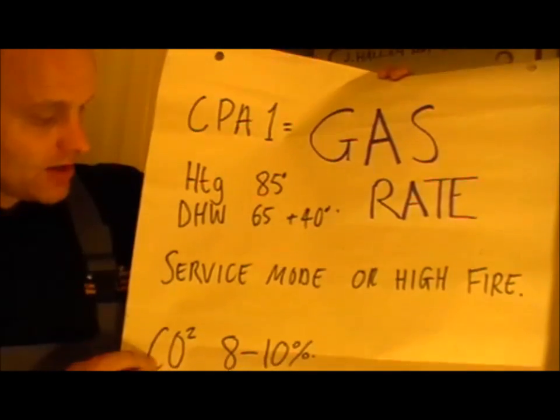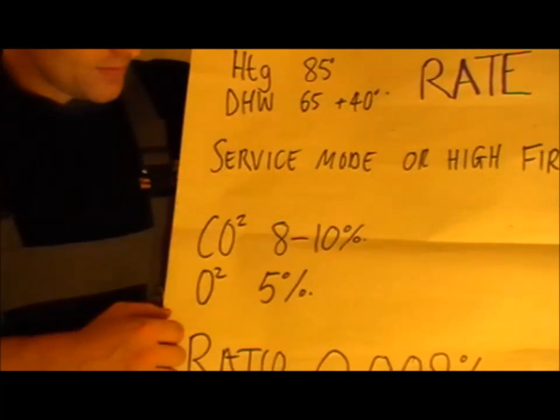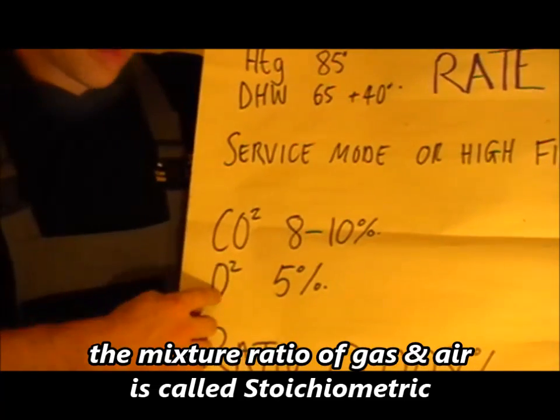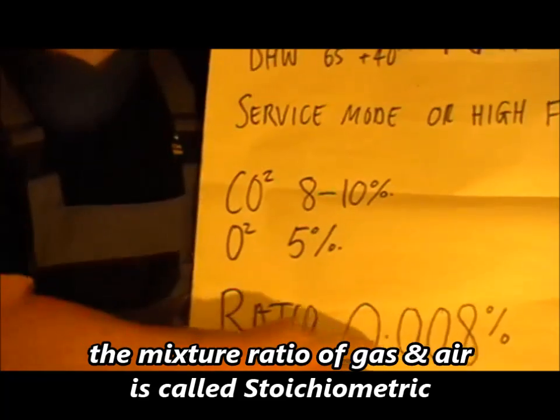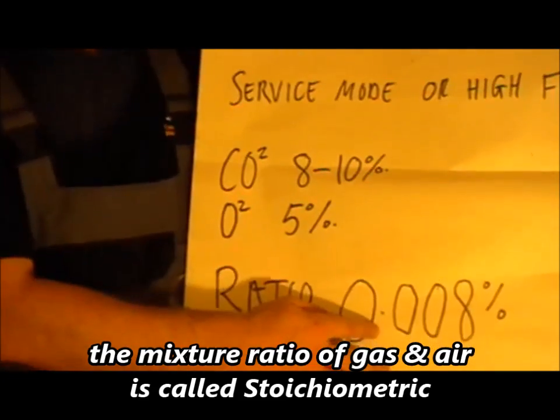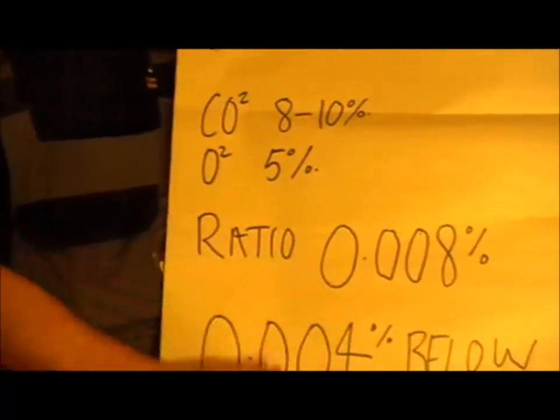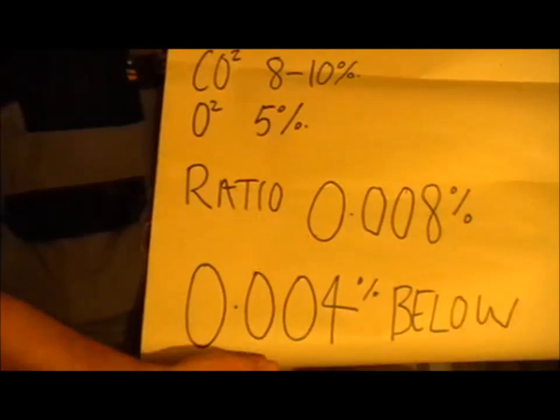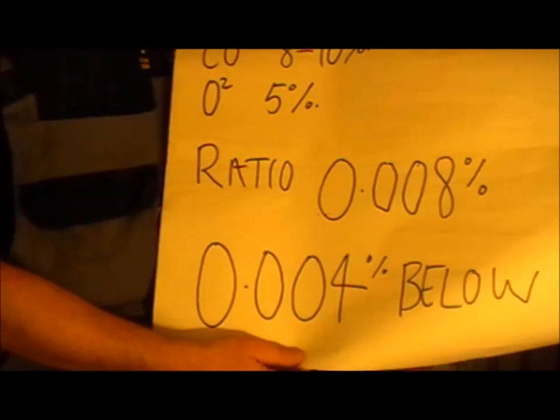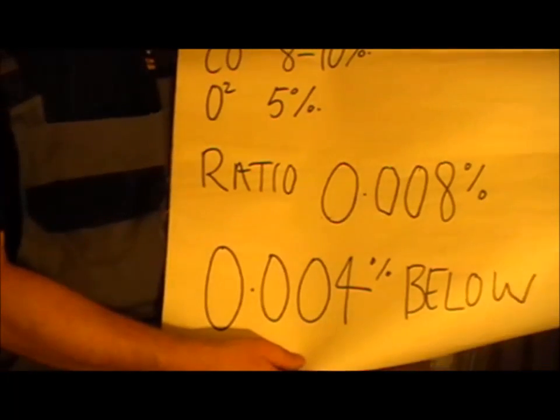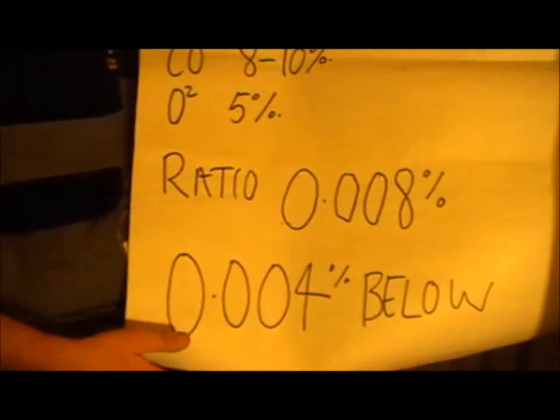We're looking at carbon dioxide of 8 to 10 percent, oxygen at 5 percent, and a ratio of 0.008 — it has to be below that legally. What is good is to be below 0.004; that is very good. Display that. If it's between these figures, the appliance really needs to be stripped down and serviced.